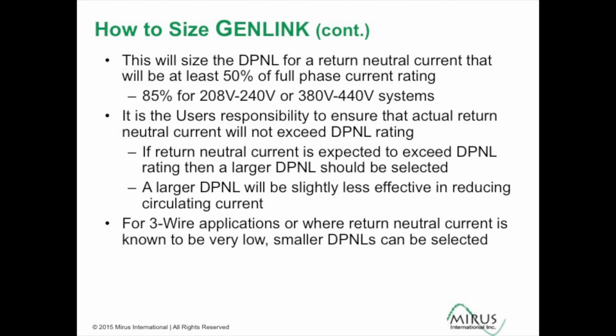When we select from this table, that will size the DPNL for return neutral current. That will be at least 50% of the full phase current ratings. For power systems that have more phase to neutral loads, such as a 208 or 240 volt system or a 380 to 440 volt system, we size it so that it's 85% of the power system rating. But it is the responsibility of the users applying them to make sure that the return neutral rating is high enough to handle the return neutral current.